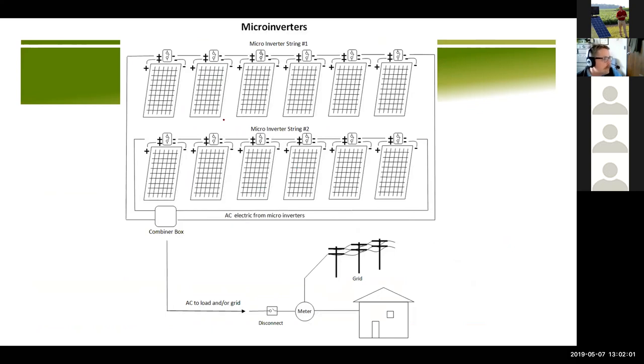The last way is maybe the most simple to install, but is the highest cost, and that is putting a small inverter on each one. So each solar panel has its own inverter, and it thus is its own kind of little mini system, and those systems are strung together. And again, in this case, if I were to have shading, I only lose just one solar panel. Also, when the electricity goes out, I'm losing that on an individual solar panel basis. The electricity is out. These are dead. These lines are dead. Even in between them is not functioning. So it's very good from a safety standpoint, also for roof mounted systems, but also is fairly simple to install. Okay, those are the three and some basic design criteria with respect to why you might choose the different ones.